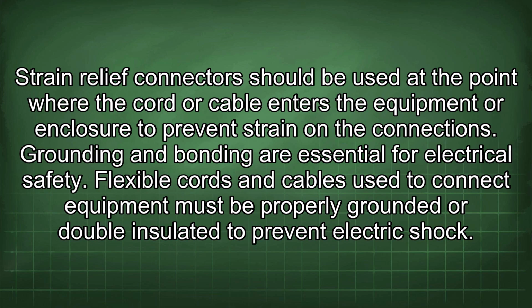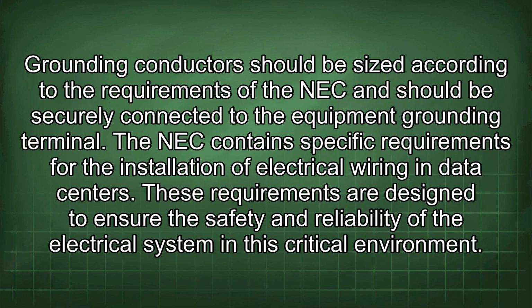Grounding and bonding are essential for electrical safety. Flexible cords and cables used to connect equipment must be properly grounded or double insulated to prevent electric shock. Grounding conductors should be sized according to the requirements of the NEC and should be securely connected to the equipment grounding terminal.